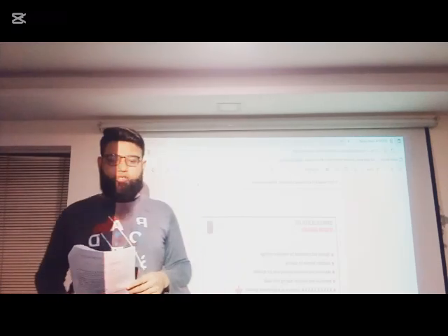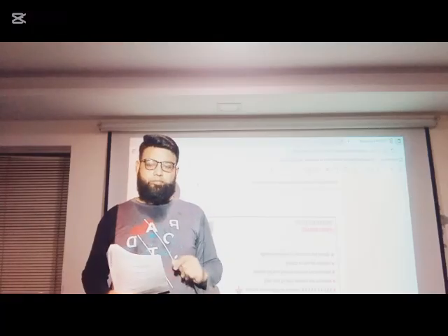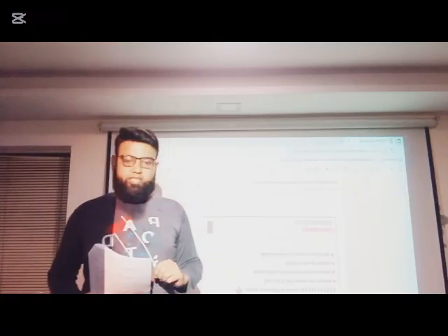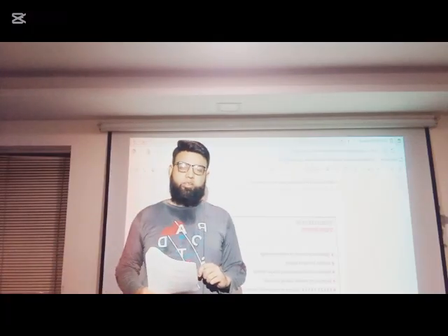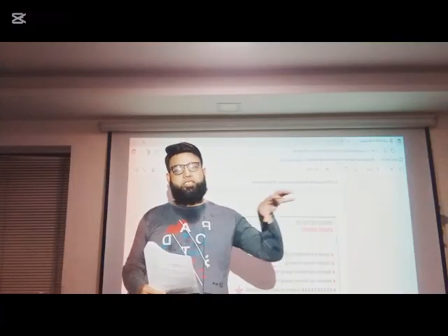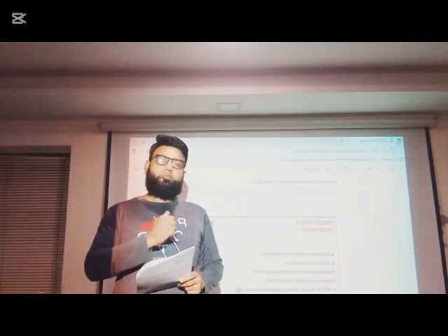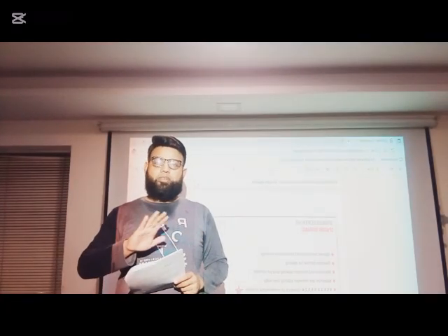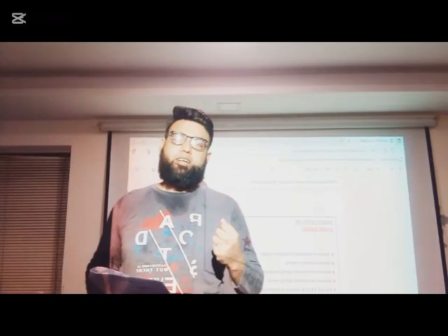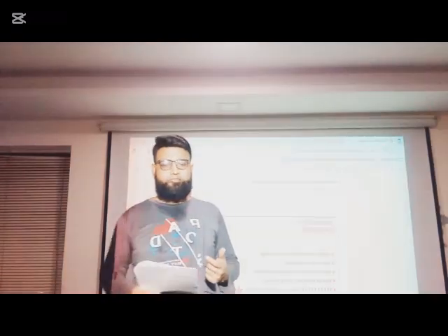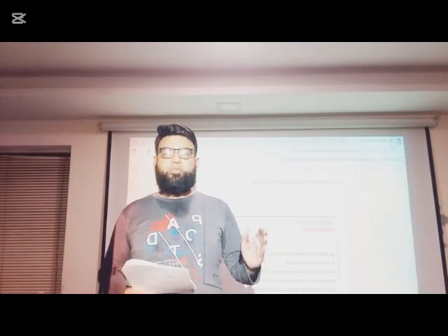Sprinklers must protect the area as per NFPA objectives. So it is the main principle of the sprinklers. The second is that no additional protection is needed for architectural features without additional floor area. If the floor area is not increased, then the number of sprinklers decided as per the spacing formula may not need to be increased. So what is the formula for the calculation of the spacing of the sprinkler? The formula is AS is equal to S into L.